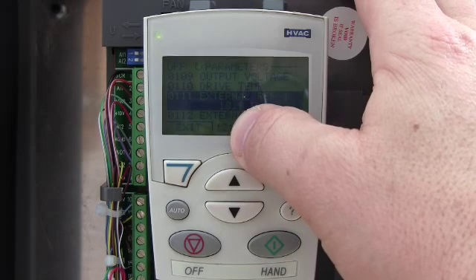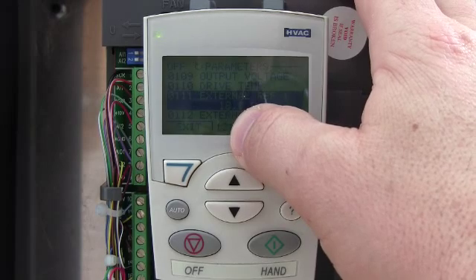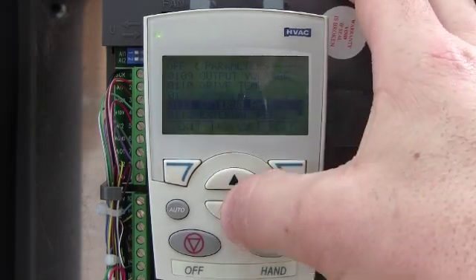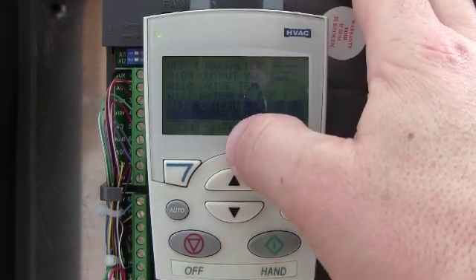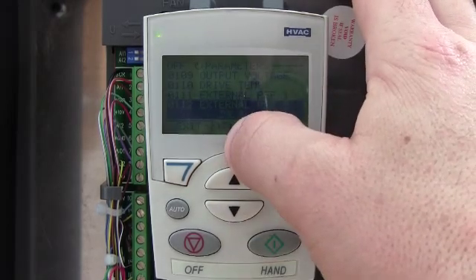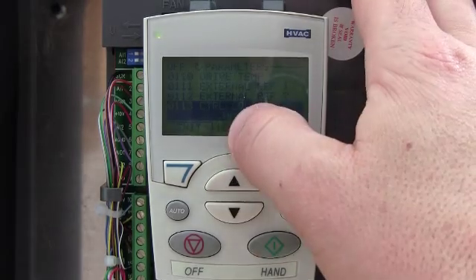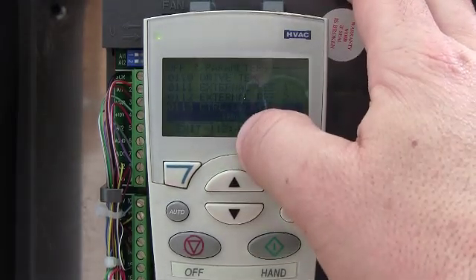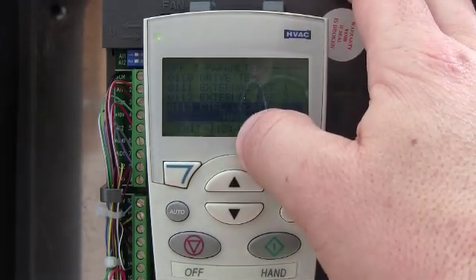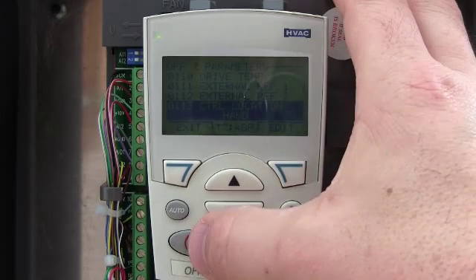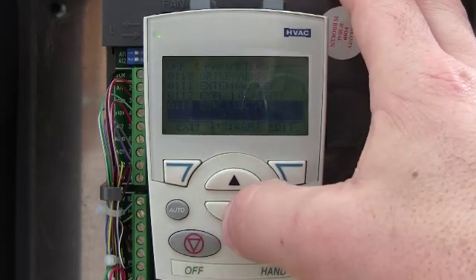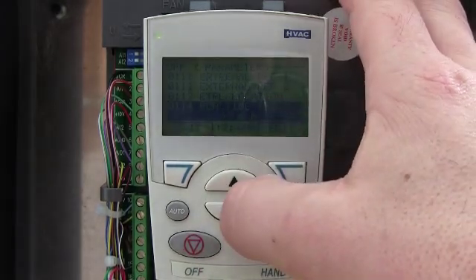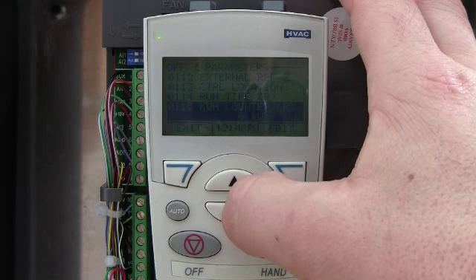Reference one is basically what the drive is going to run at in reference one mode. Reference two, it's showing 29%. Control location — this is very handy. Right now it says that it's in hand mode. Run time — this drive only has six hours on it.